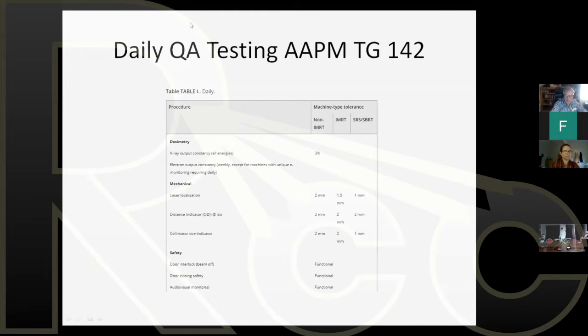And notice how for machines which are used for stereotactic radiosurgery or stereotactic body radiotherapy, the tolerances become tighter as the precision of the machine becomes more crucial with delivering these very, very high single doses or several doses of high dose radiation. And that was a big change with TG142. It established much tighter mechanical tolerances for machines that are used for stereotactic radiosurgery or SBRT.